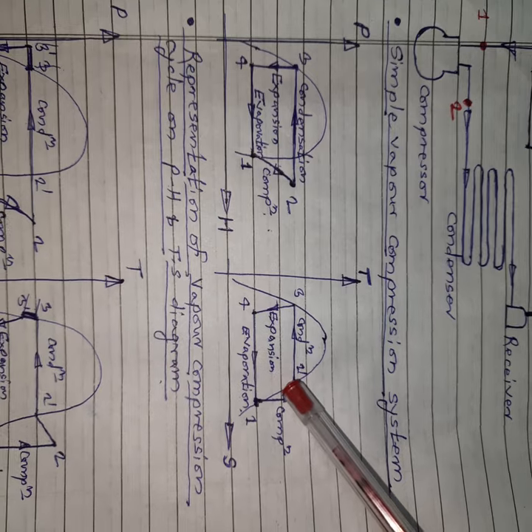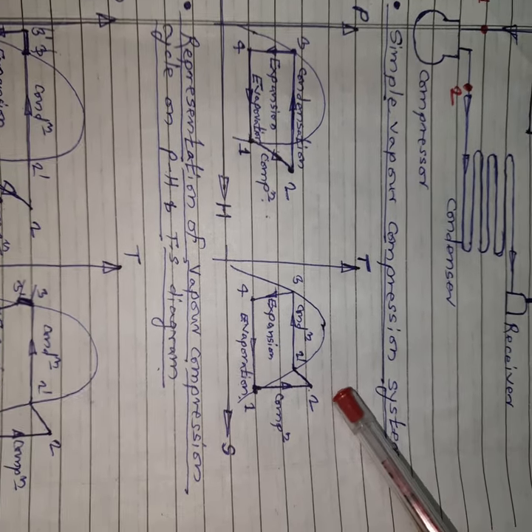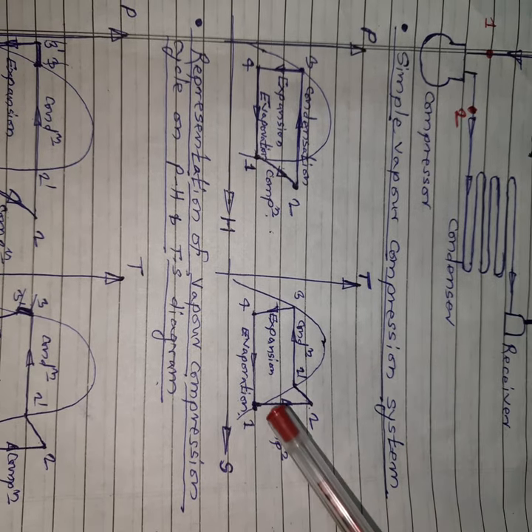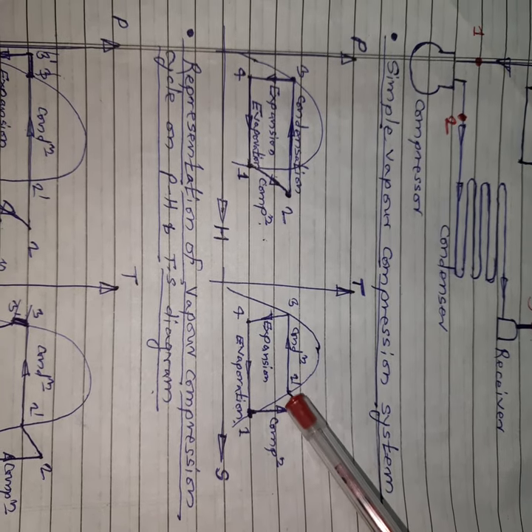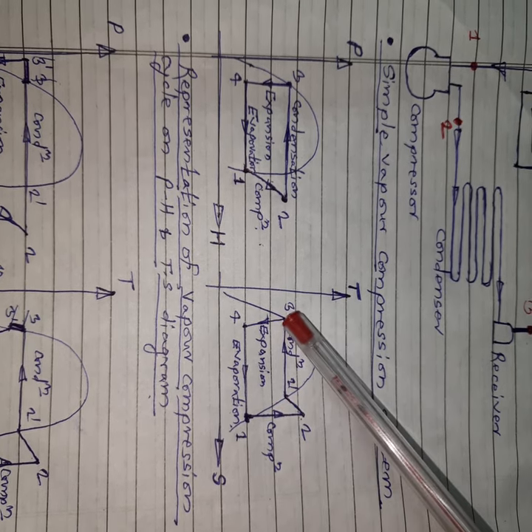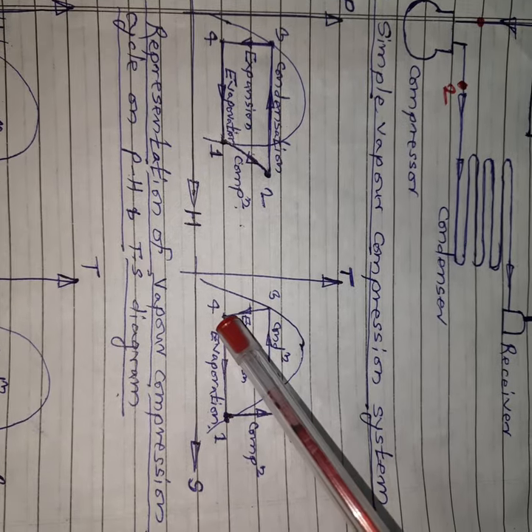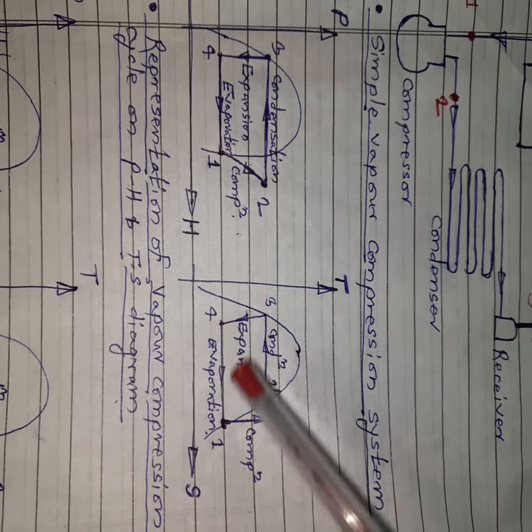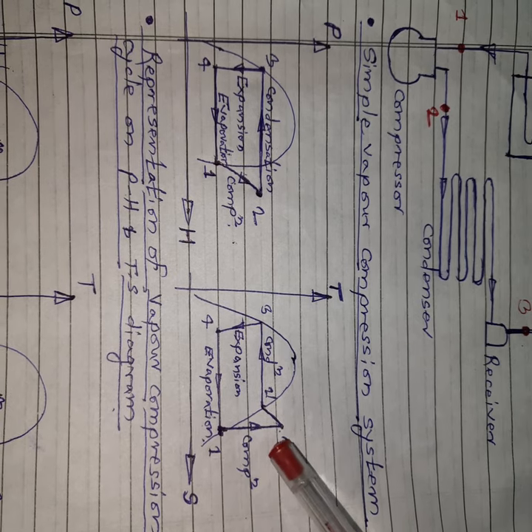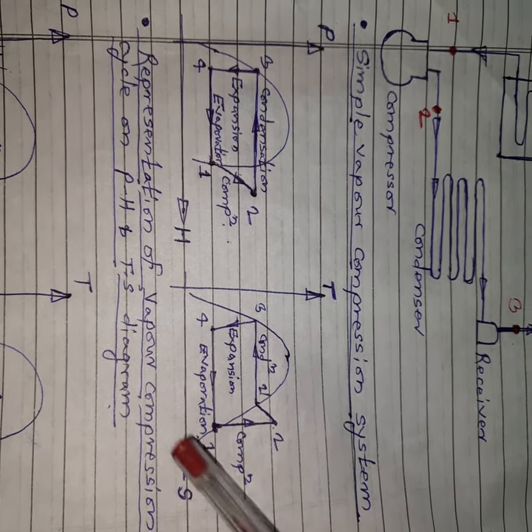The same diagram is shown on the TS diagram. 1 to 2: adiabatic compression — entropy remains constant and temperature rises, shown as a straight line. 2 to 2' is removal of sensible heat; 2' to 3 is removal of latent heat. 3 to 4 is the throttling process. 4 to 1 is the constant pressure evaporation process. This is the representation of the vapor compression cycle on the TS diagram.